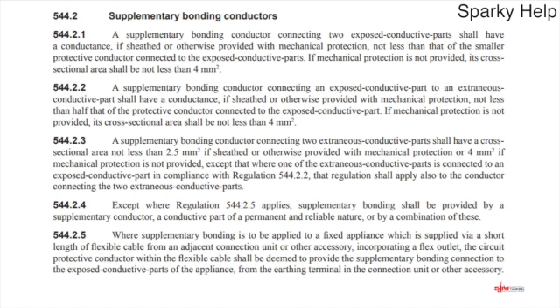The next one down says a supplementary bonding conductor connecting an exposed conductive part to an extraneous conductive part shall have a conductance, if sheathed or otherwise provided with mechanical protection, not less than half of that of the protective conductor connected to the exposed conductive part. If mechanical protection is not provided, its cross-sectional area should not be less than 4mm. So this is talking about going from an exposed to an extraneous part, that's structural steel or a pipe or something like that. And if you've got conductors going into it, it's got to be not less than half of the protective conductor of the circuit. If you do provide mechanical protection, then you can do that. If it's not got mechanical protection, then it becomes a 4mm.